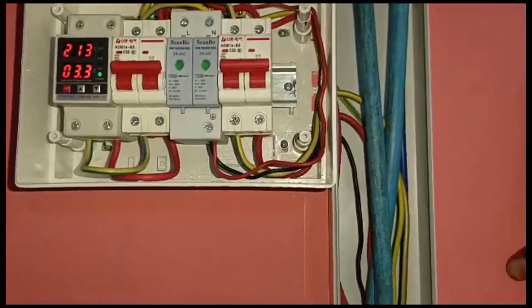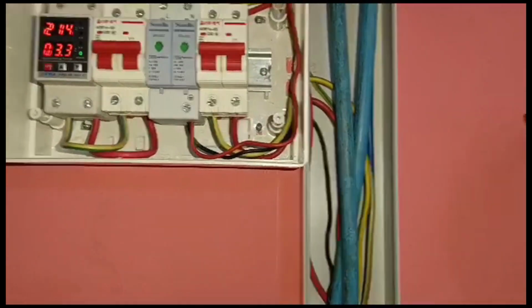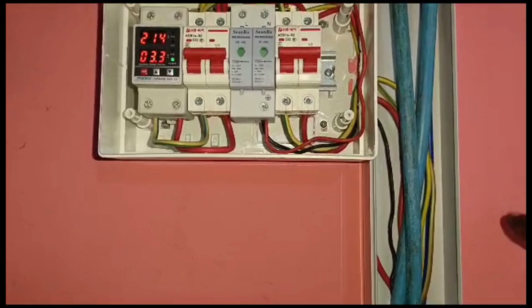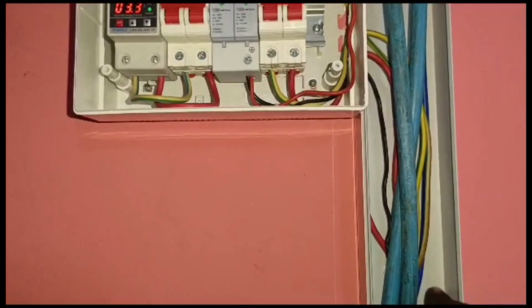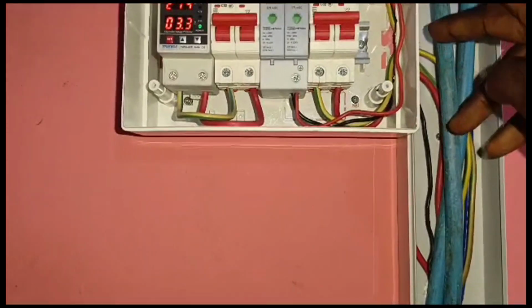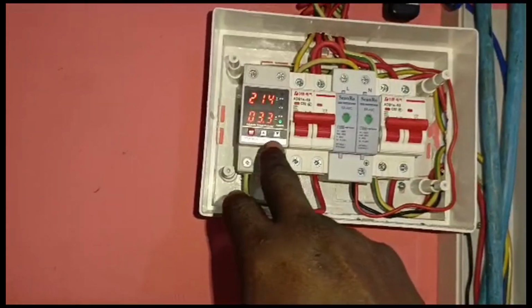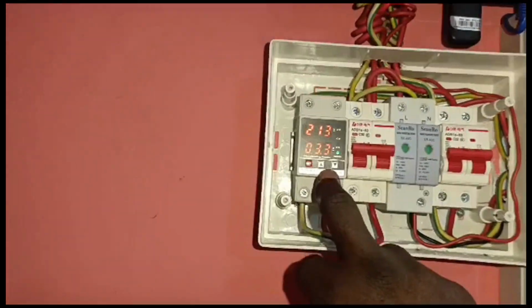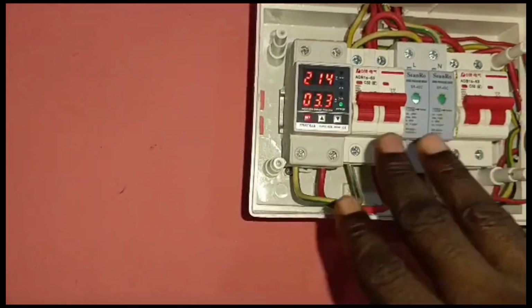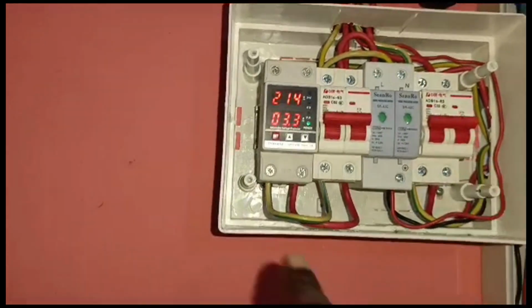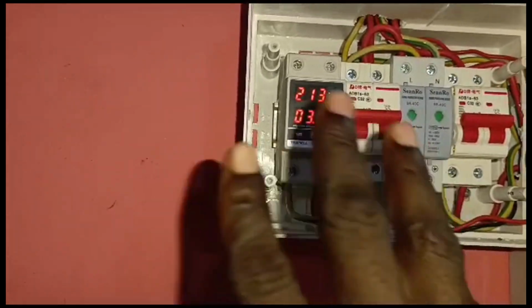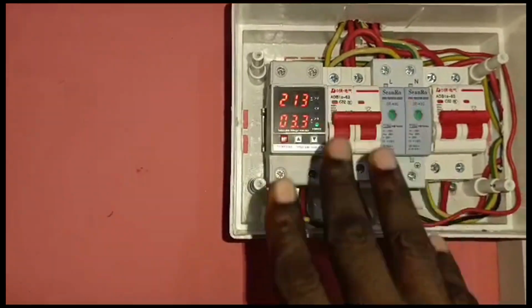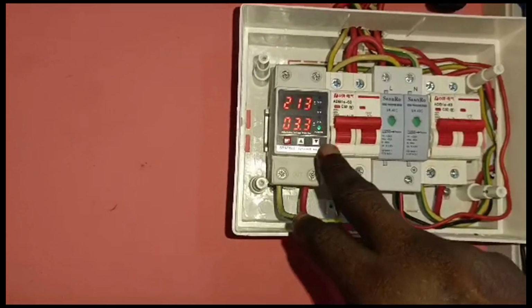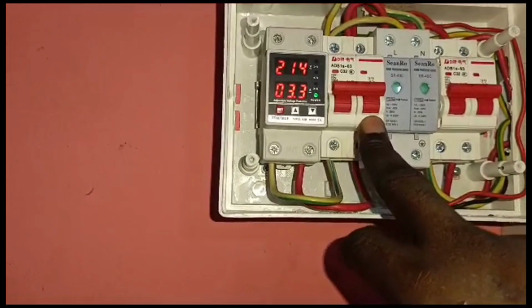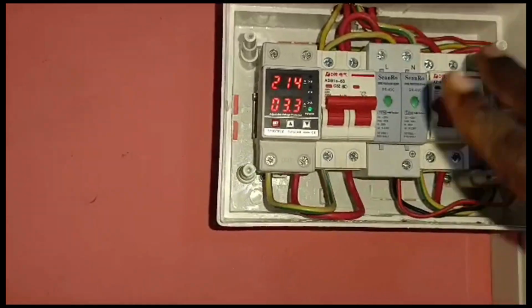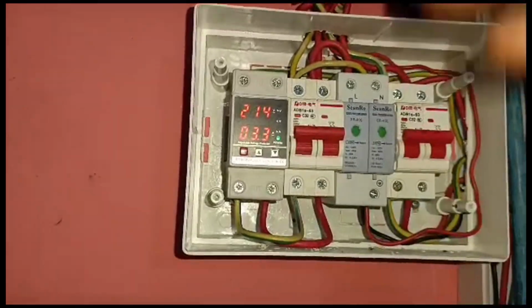So the home consumer unit is on the other side of this wall. The inverter is fed via a 30 amps circuit breaker. It comes in through this cable here. It passes through this voltage regulator, which serves as the first line of defense for the inverter. It has over voltage, under voltage, and current protection. From here it comes through this circuit breaker, which serves as a switch, an isolator in case you want to isolate the grid from the inverter.